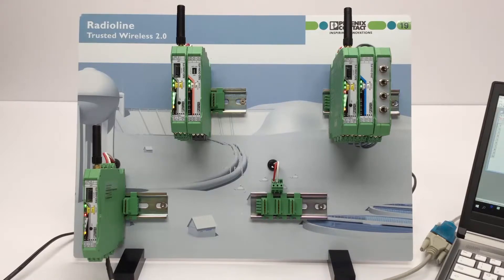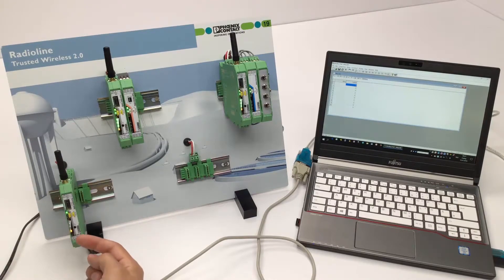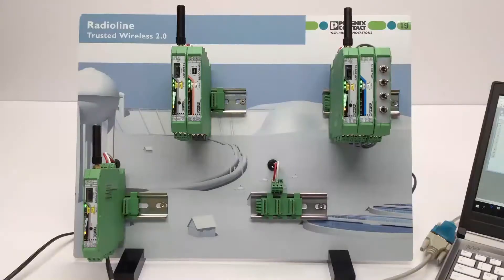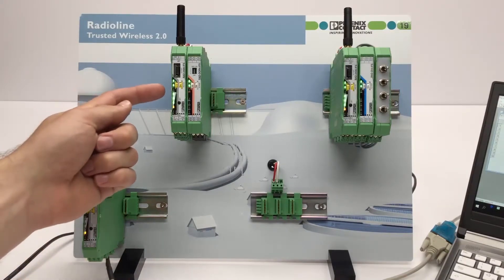With the Modbus Poll software, a Modbus communication to the radio master is now established. If the serial cable is connected and the interface parameters are set correctly, the RX and TX LEDs will flash on the Radioline master. Since there is Modbus communication present, the red ERR LEDs on the radio modules will turn off. The update time of the central Modbus register in the radio master can vary depending on the frequency band, network size, and signal quality of the radio links. This must be considered in the controller to make sure up-to-date data is being read.